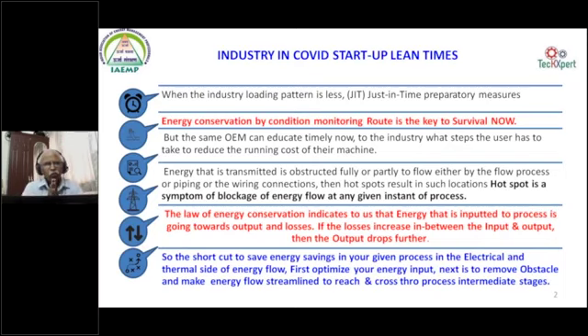So first is to just trim or optimize the input. See, I am getting a transformer in my industry, which is receiving some 380 volt to 470 volt, say around 450 volt in the nights and 415 volt in the daytime, and 380 also sometimes in the peak of the daytime. Yeah, the electricity at the transformer definitely will pin down the voltage at 415 volt plus or minus 5 volts. So automatically trimming the energy input to the process is one aspect. This is a shortcut, and it doesn't consume much money. Only you need to optimize the energy input to the process.